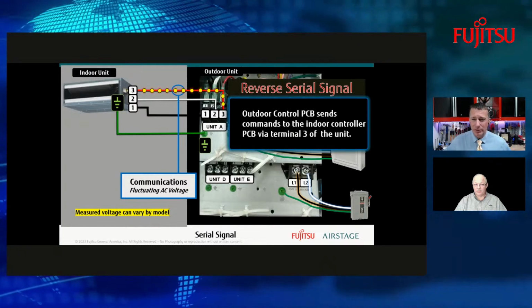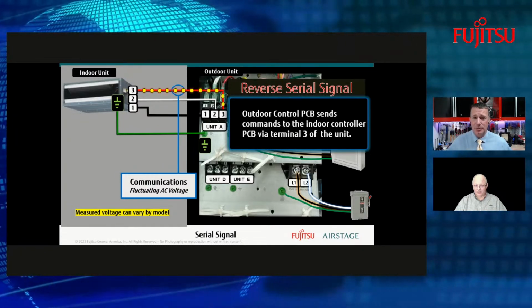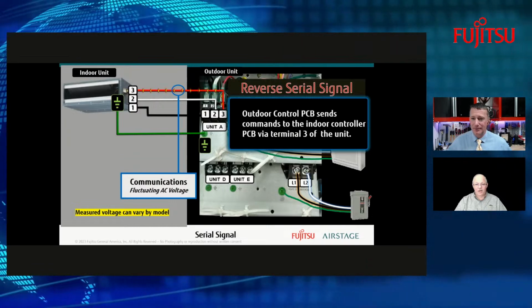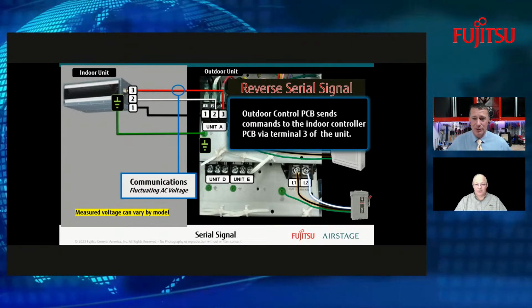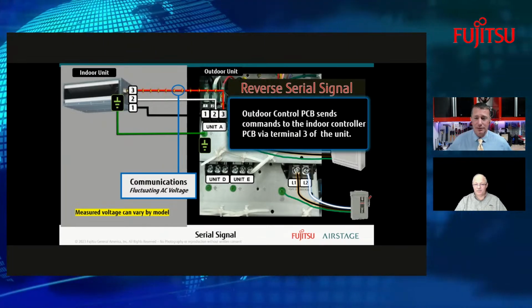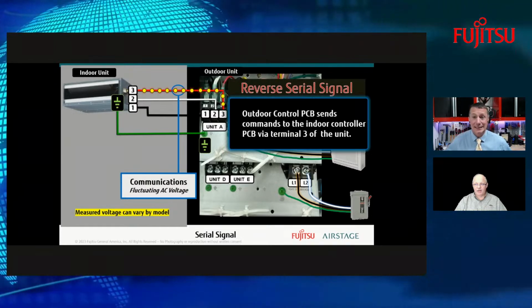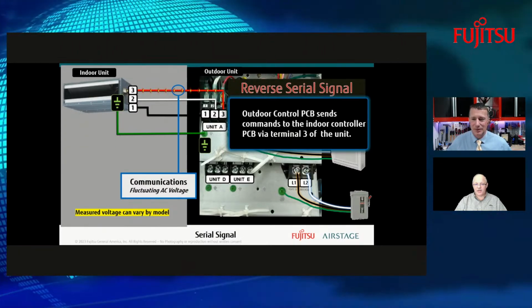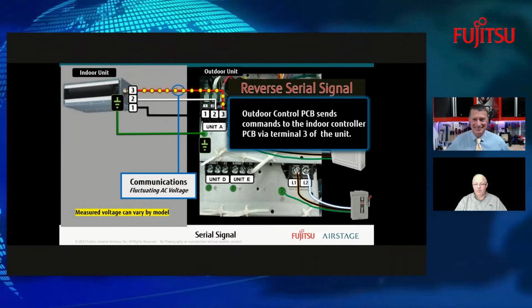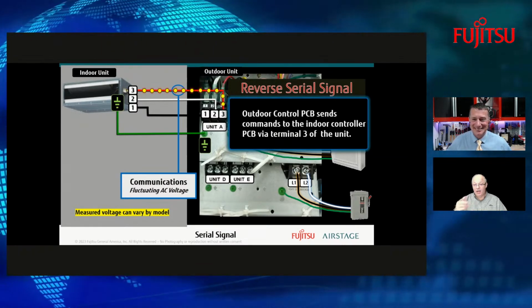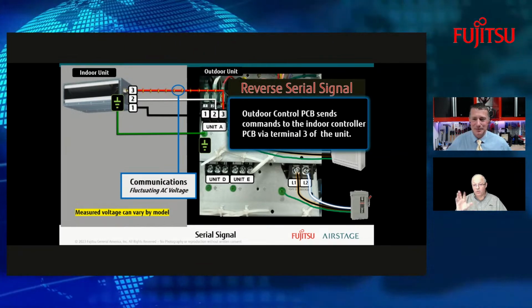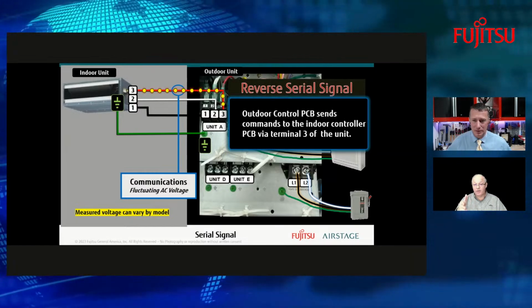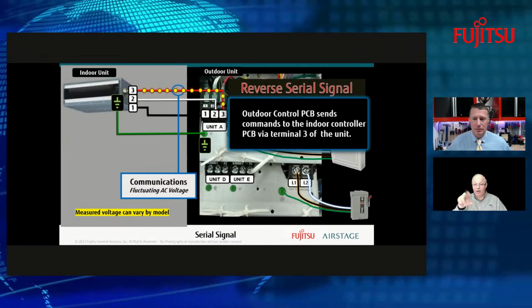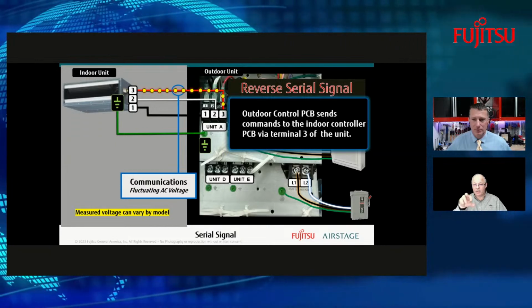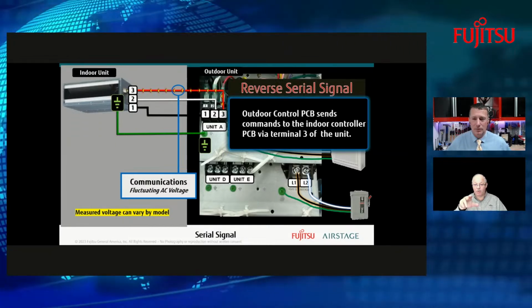So if I put my meter on volts AC, I'm going to see a fluctuating voltage between number 2 and number 3. Yeah, and it'll be jumping around like crazy. Okay, so some meters may not even be fast enough to pick it up very easily. It'll pick it up. It's whether your eyes can focus on it, right? But the way I always do that, I just look at the meter, and my brain says, don't look at the whole range. Look for the lowest number you see first. There you go. So it's sitting there jumping around, and if I see 40, 70, 60, I'm looking for the lowest number, and I'll write that down.